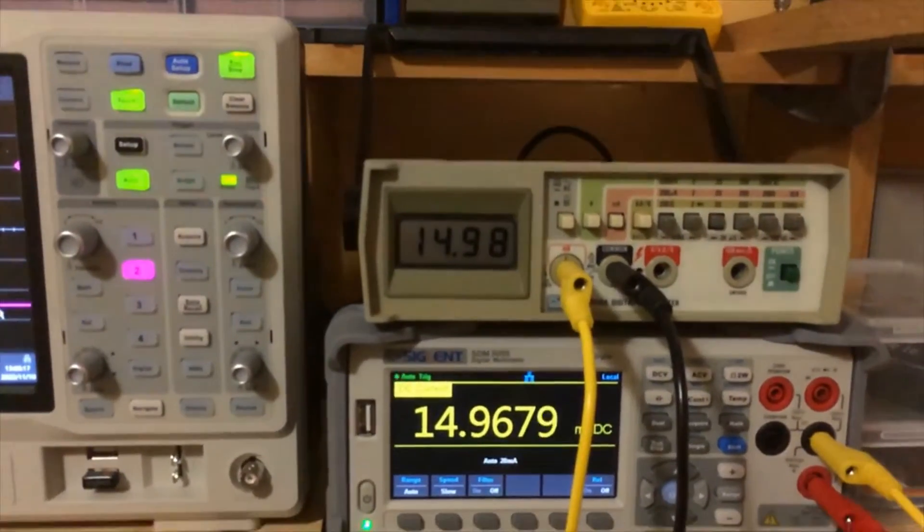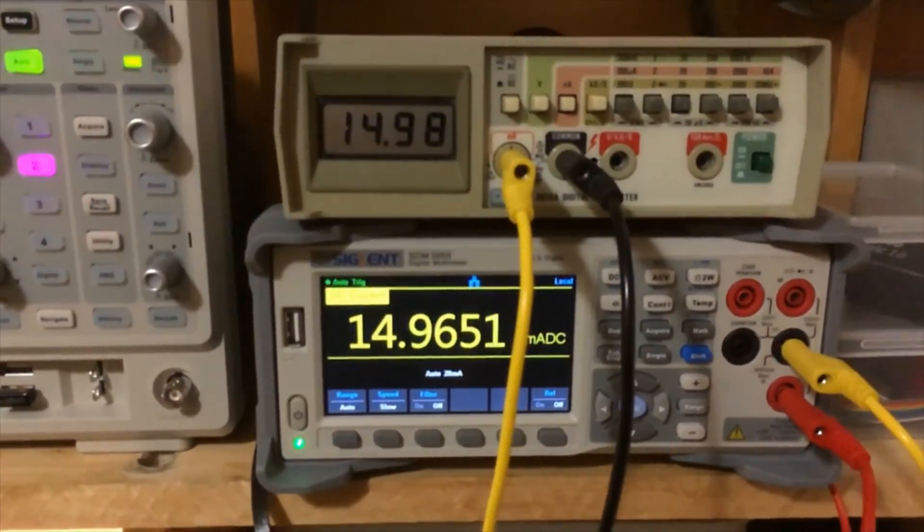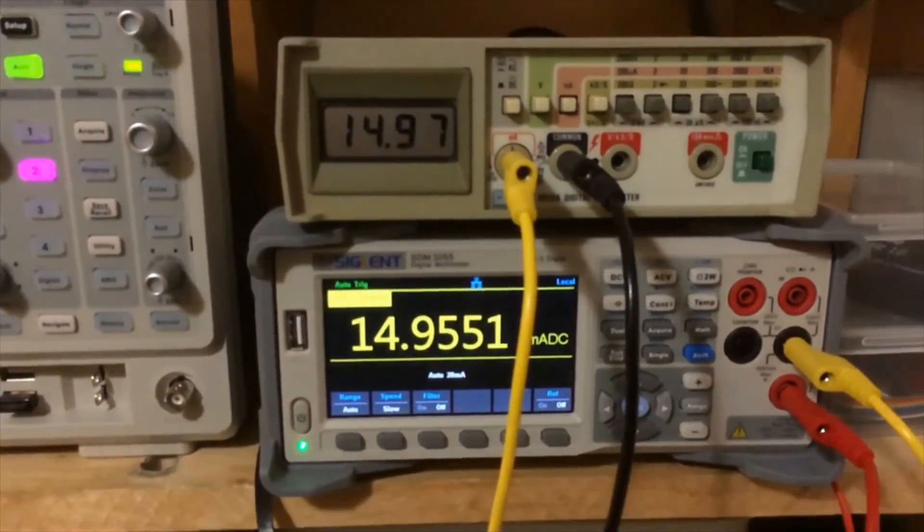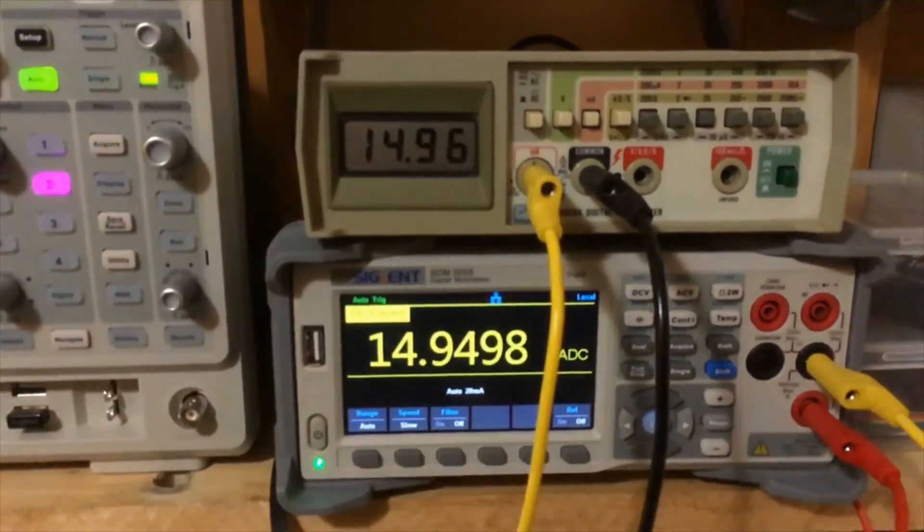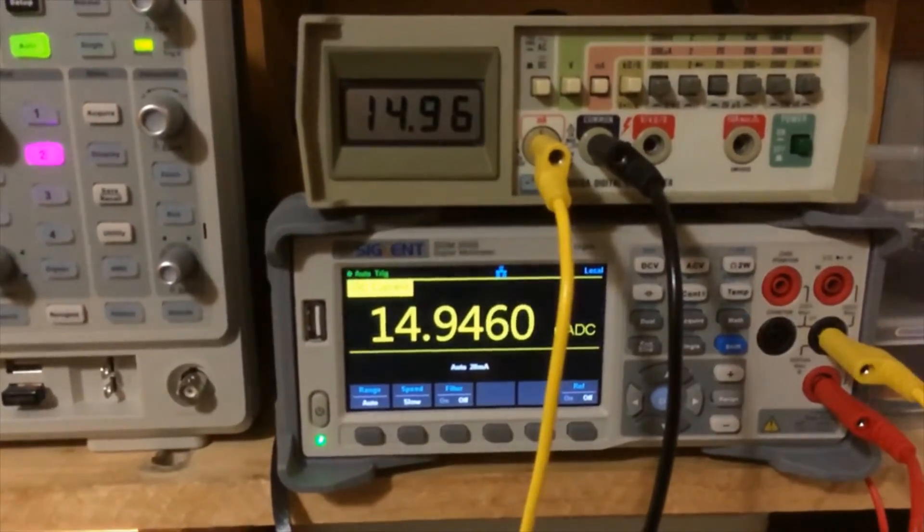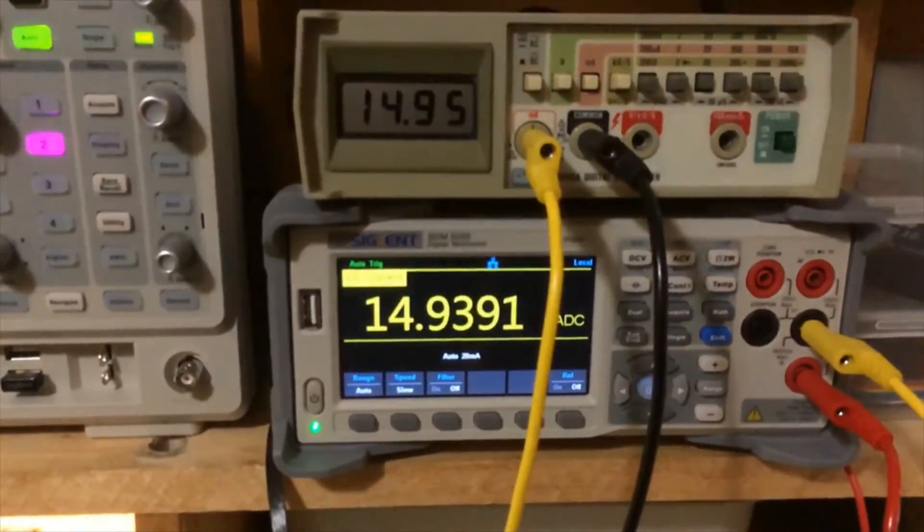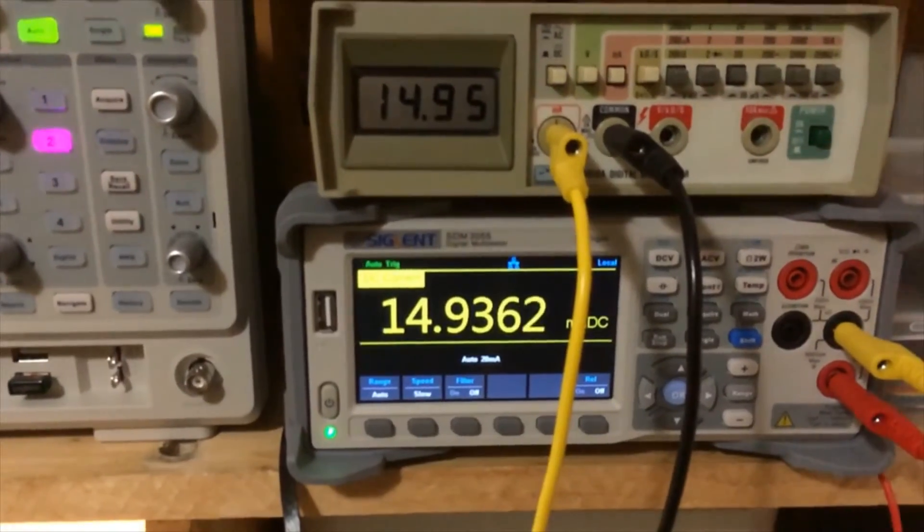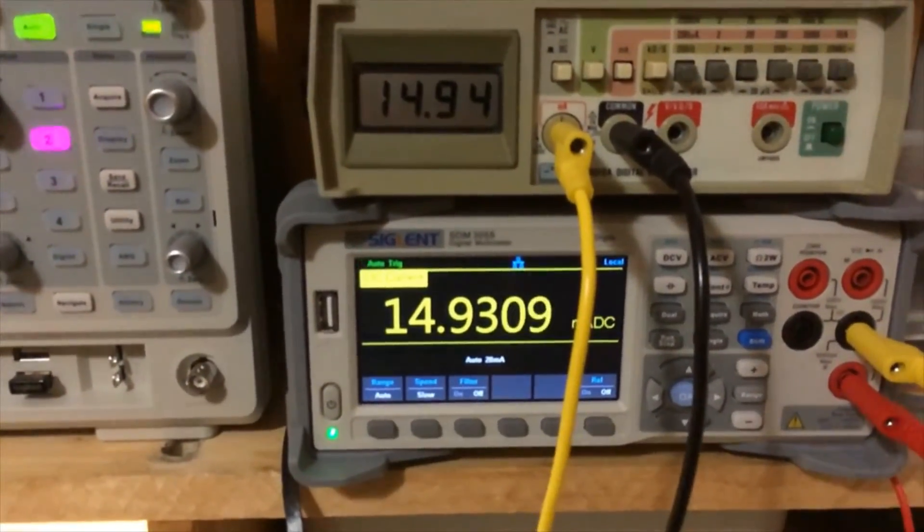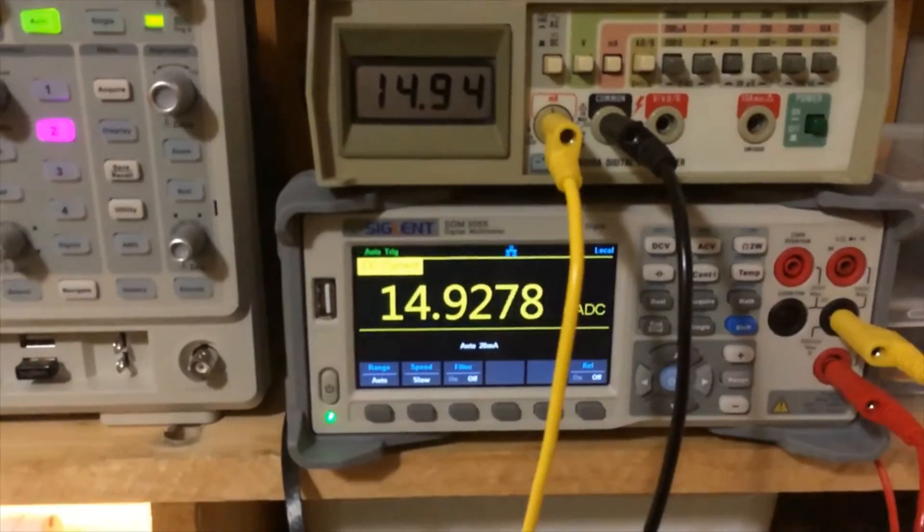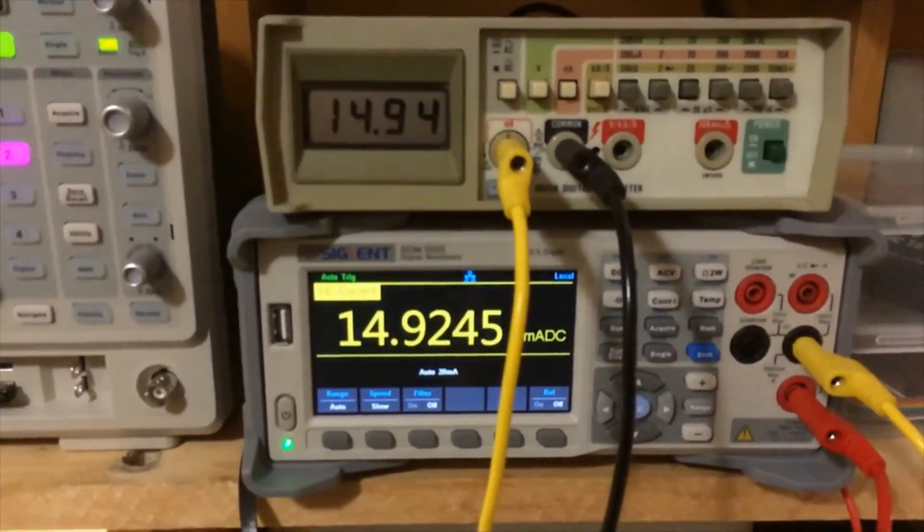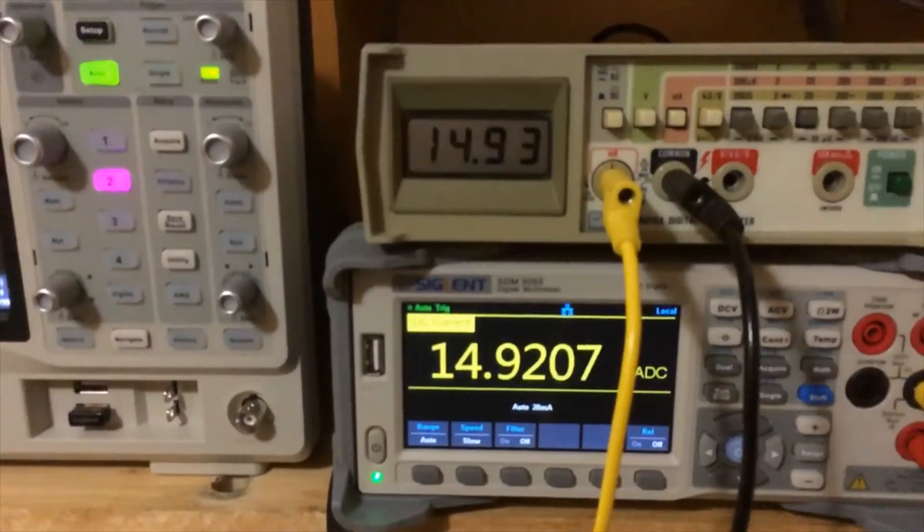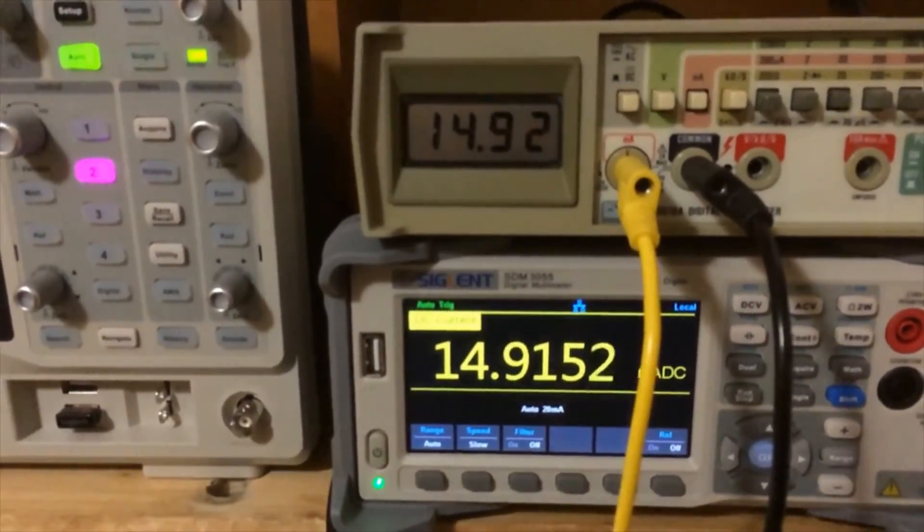Okay, so here we are, we're 14.95-96 milliamps on both of them. So we're well within the margin of error here. I'm happy with this. We're less than one percent, or less than one tenth of one percent out. That's very good. Let's try a little bit more current here.